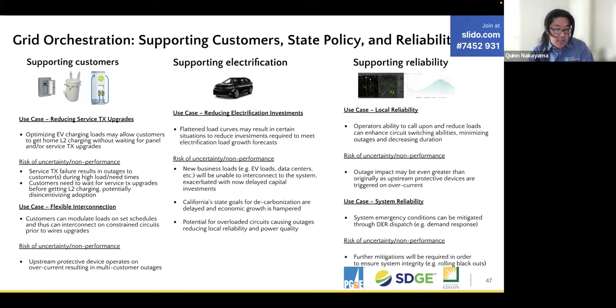But when you really peer into it, that constraint may only occur during this particular day, in these particular hours, in a particular year. And really what you can do is set schedules, real-time, day-ahead type schedules that enable you to say, okay, I know you wanted 4 megawatts all the time, but tomorrow for these hours, maybe if you can just get 2 megawatts and manage through the charging process during that period of time, we can get you interconnected tomorrow.